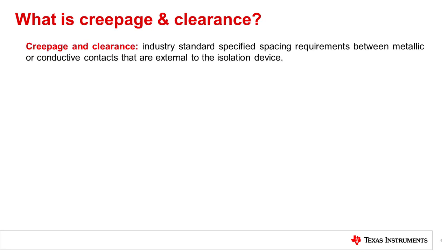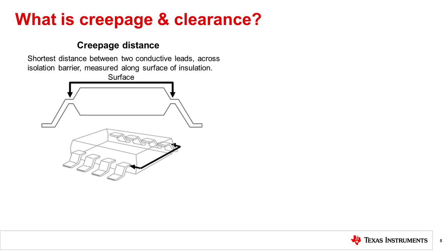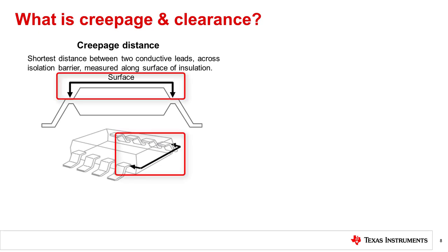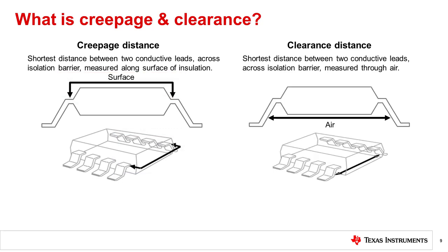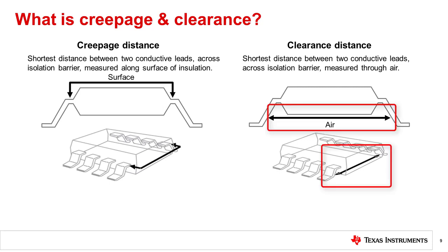Creepage and clearance requirements are industry-standard specified spacing requirements between metallic or conductive contacts that are external to the isolation device. Creepage is defined as the shortest distance between two conductive paths measured along the surface of a solid insulation — the shortest path is typically found around the end of the package body, between conductive pins or leads. Clearance is the shortest distance between two conductive parts measured through air, typically measured on a device package between pins under the body of the package.